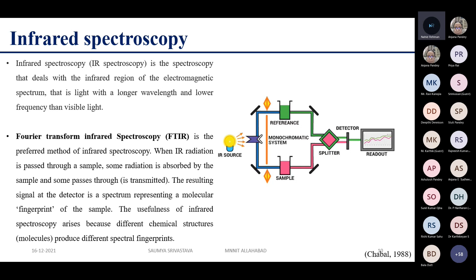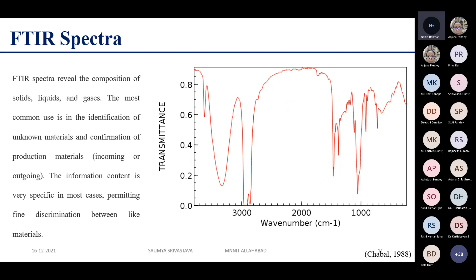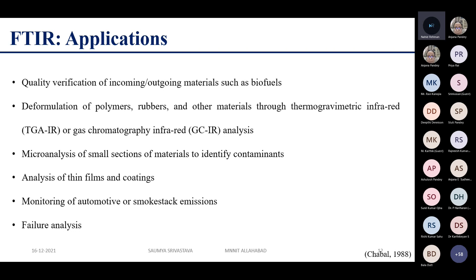The general FTIR spectra we get reveals the composition of solids, liquids, and gases. The most common use is the identification of unknown materials and confirmation of the producing materials. FTIR is generally used to verify the quality of materials such as biofuels, for the analysis of thin films and coatings, microanalysis of small sections of materials, for identification of contaminants, and the deformulation of polymers and rubbers.